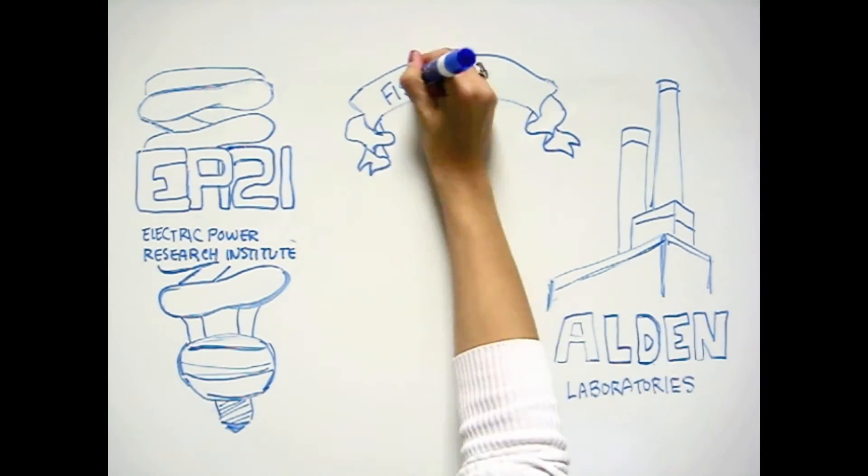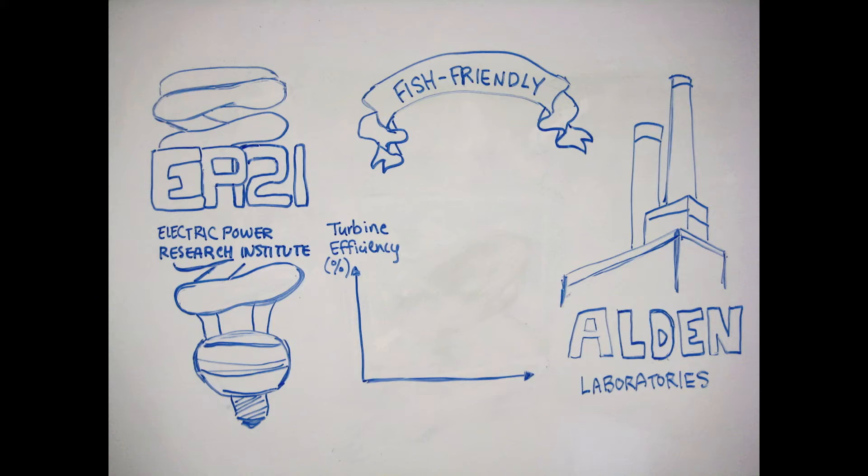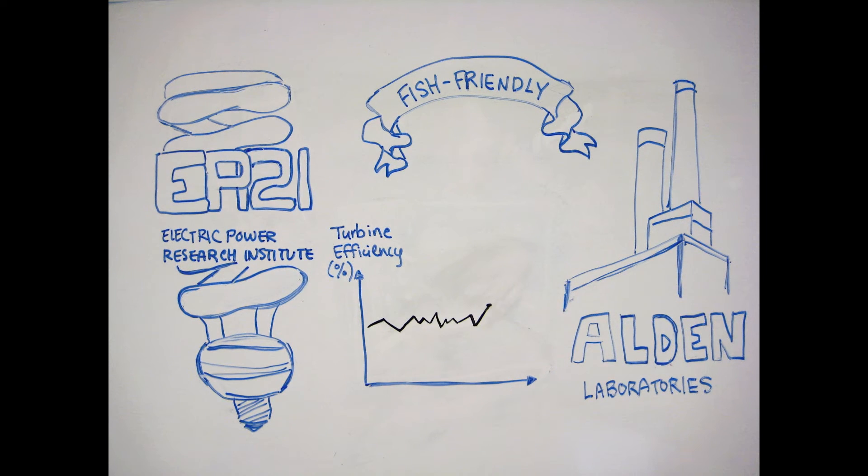These turbines exceeded expectations. Overall fish survival rates reached above 98%, a significant increase from the 80% survival rates from a traditional turbine. Additionally, no power efficiency was compromised. It converted 94% of the water's energy into usable electricity, even more efficient than some traditional turbines.